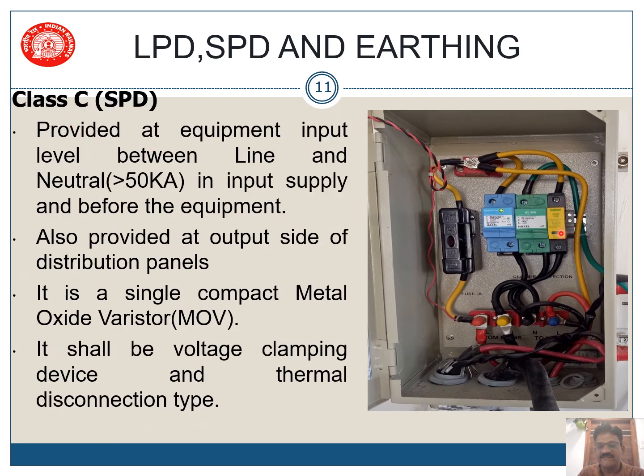If you take this, this is the class C protection. It is again provided at the equipment input level between line and neutral. Here, between line and neutral, it is provided with a protection range of greater than 50 kA in the input supply and before the equipment. It is also provided at the outside of the distribution panels. Whenever supply is going outside, 24 volts external, 110 volt DC, 110 volts AC, which are going outside, then also we provide these class C protections.